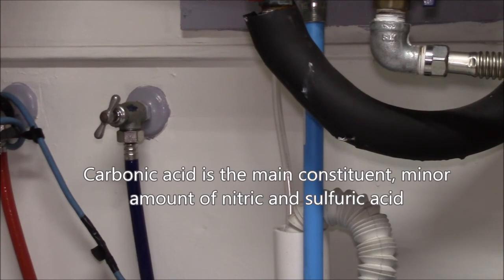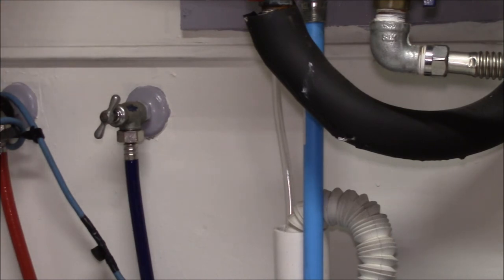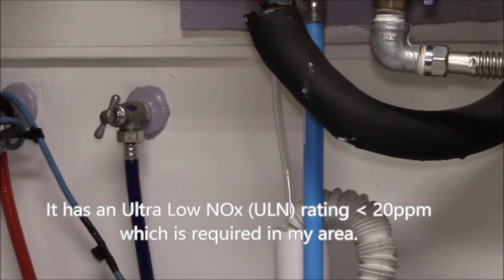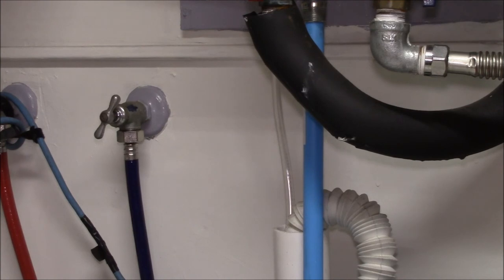Natural gas, methane CH4, there's really not much in there. I guess you have a little bit of the odorant that they put in there has some sulfur in it, but that's like a really low concentration. So you might get a little bit of sulfur dioxide coming out of there with sulfuric acid. And this heater is low NOx, so it's got very low nitrogen oxide output. So yeah, maybe other heaters, higher NOx heaters that run at higher temperatures or higher combustion pressures, might have more NOx.